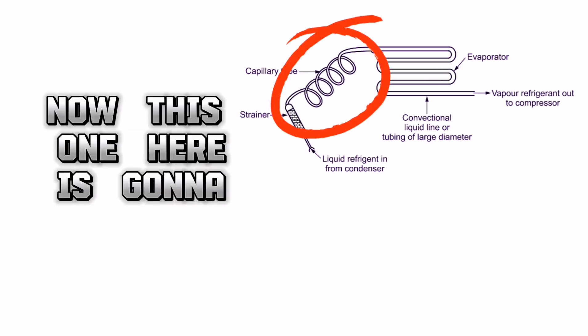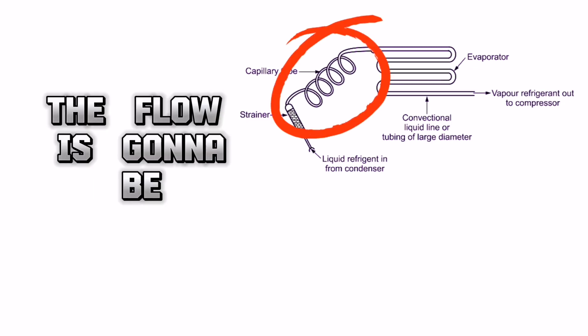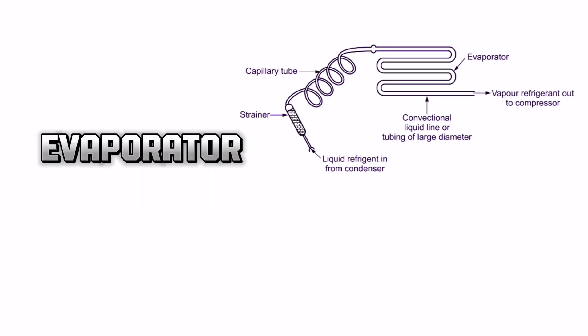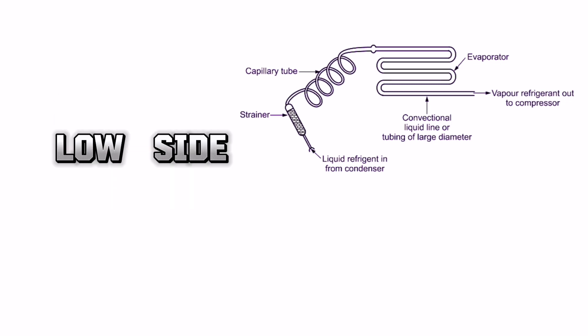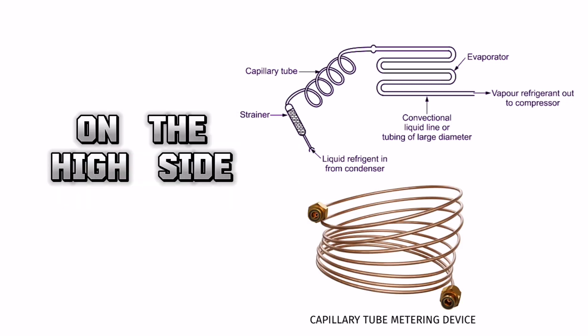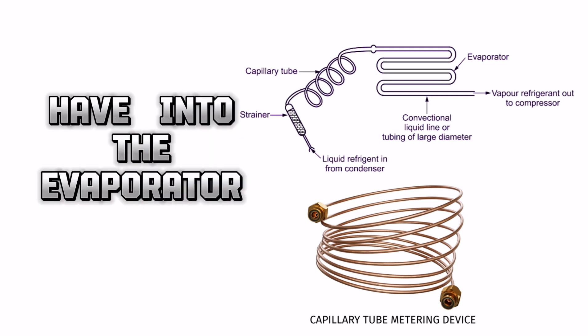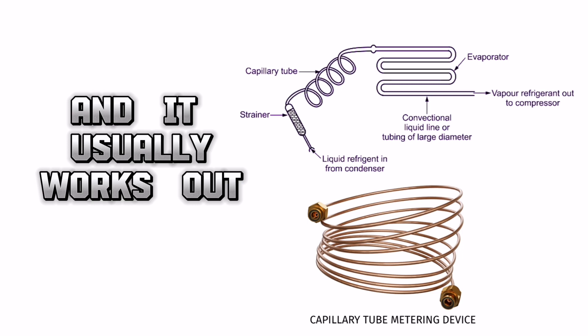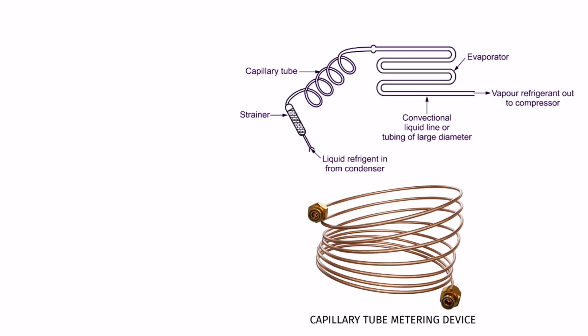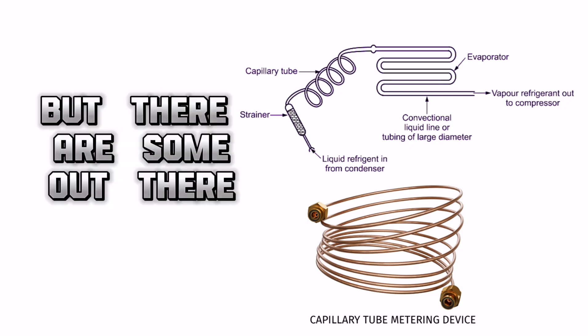Now, this one here is going to maintain what I like to say is constant flow. The flow is going to be constant going into the evaporator, but it's going to depend on the pressure on the high side and the pressure on the low side. The higher the pressure on the high side, the more pressure you're going to have or the more flow you're going to have into the evaporator. But as the pressure in the evaporator increases, it's going to restrict the flow of it coming in. And it usually works out, but this is a type of metering device that it used to be used. They don't use it that much anymore, but there are some out there.